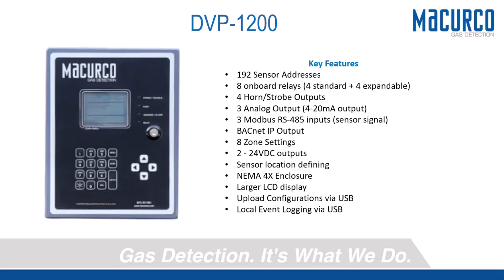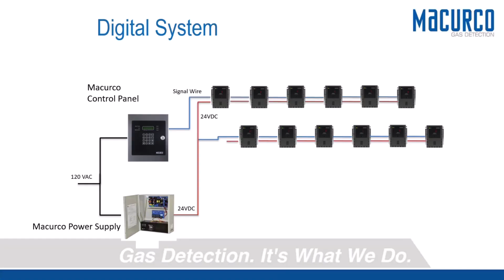For contractors that do a lot of addressable work, the key figure here is there's no T-tapping. If you T-tap our systems, it totally disrupts the communication protocol, so you'll have trouble all the time. A T-tap is when, instead of running sensor to sensor in series, you send a signal to one sensor and also split it to send to another—two signals back to one unit. You can't do that. That's called T-tapping. Stay away from it, or you'll have a headache.